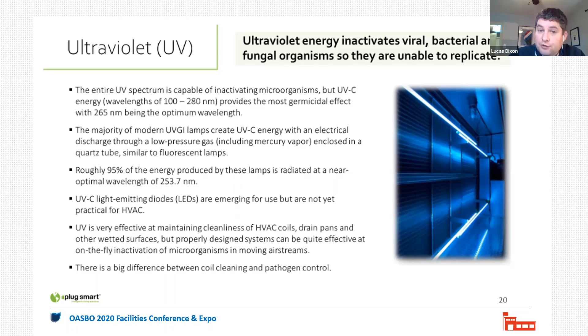UV light has been used less to actually try to kill things in the airstream as the air passes through, where you're trying to kill airborne viruses, in this case, pathogens, yes. So while it can do it, the application requires a lot more technology, more UV lights at a greater intensity to be able to do that and expose the pathogens as they move through the unit. So it's hard to use UV and make sure that you are covering your entire airstream with enough intensity to have it be effective. So it is a difficult thing to do. They do work, they do kill things, and they are quite potent.